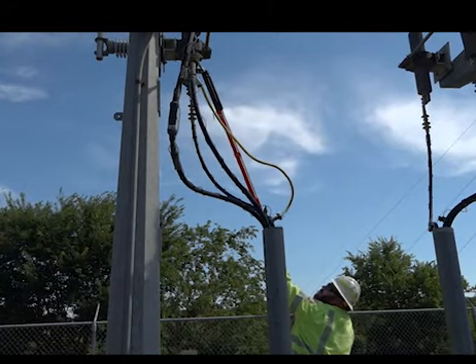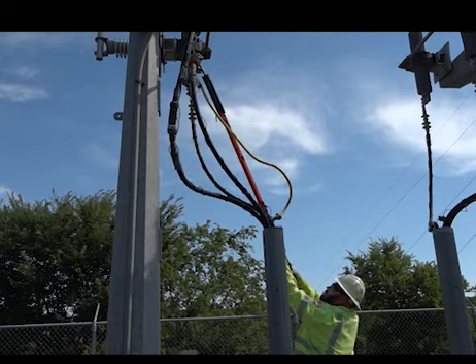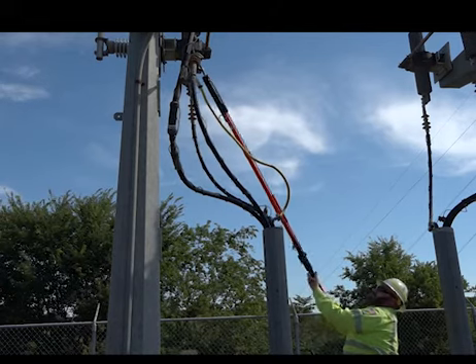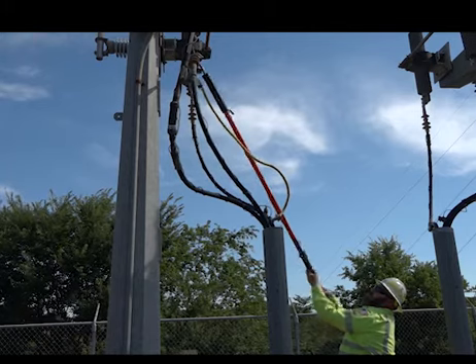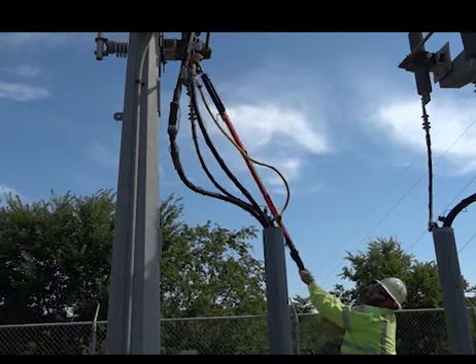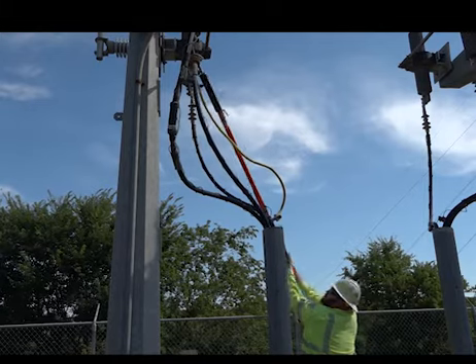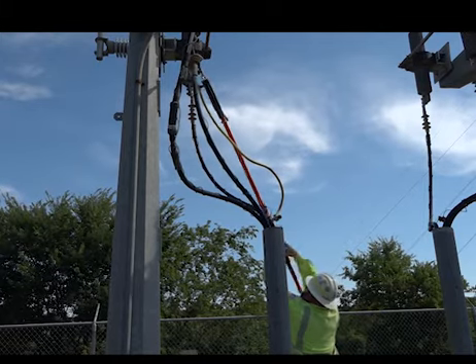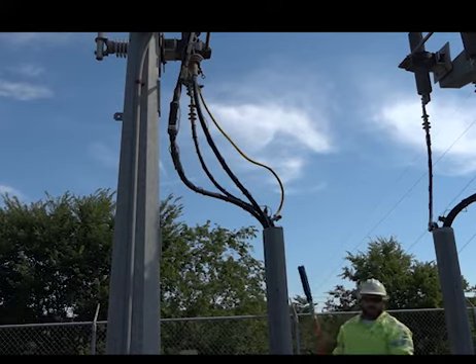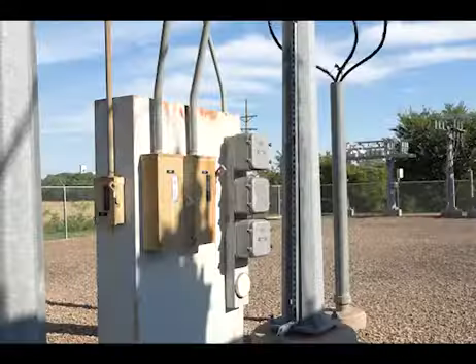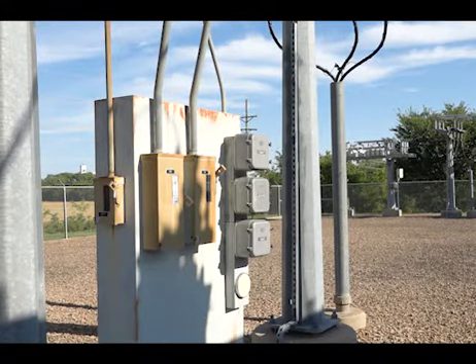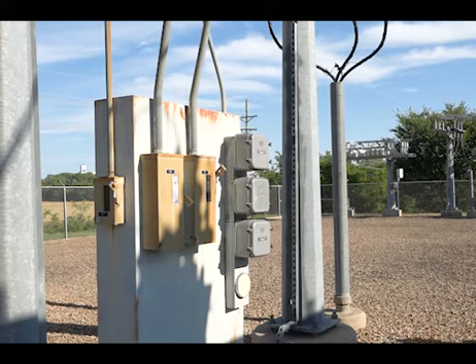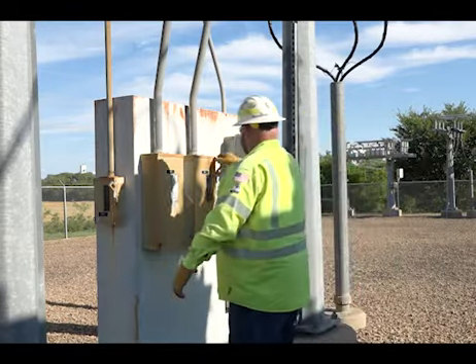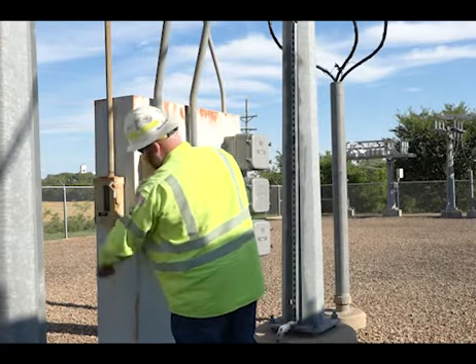Electrical hazards. Induction, capacitance, and static charges can be a serious problem in substations and can cause dangerous voltages to be present even on de-energized equipment when it is not properly grounded. Ensure you have properly sized and tested ground cables. Attach all equipment grounds to a ground riser that is solidly connected to the ground grid. Remember to isolate the bus potential transformers and station power transformers as possible backfeed sources. Do not place grounds on corona rings, conductor spacers, or bus pots.